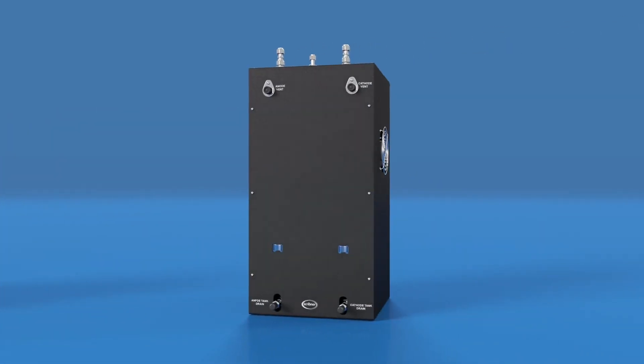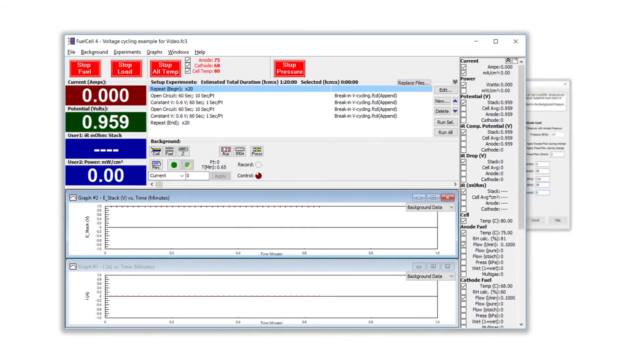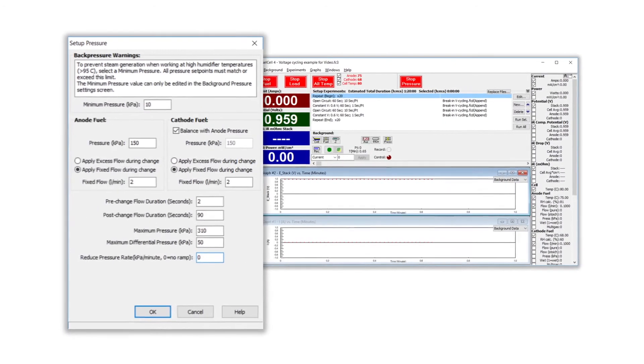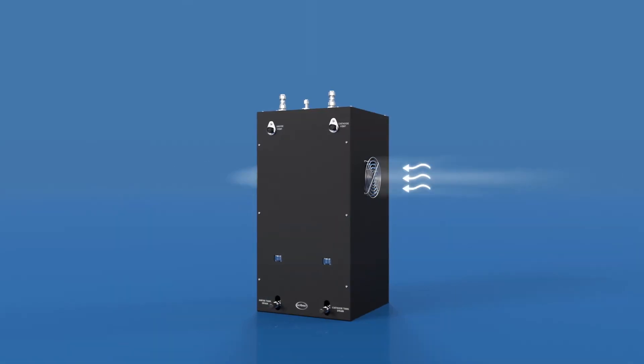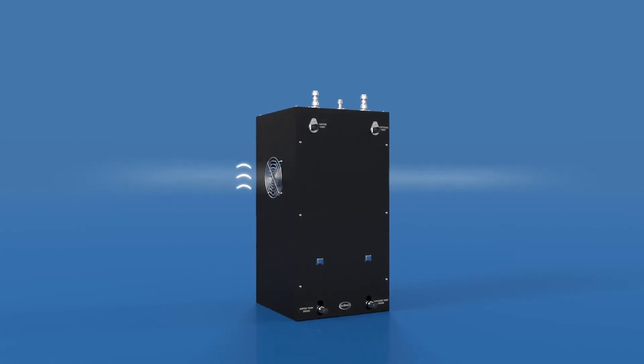The automated back pressure unit permits hands-free pressure control. The anode and cathode pressure are independently set and controlled through Scribner's fuel cell test system application software. The automated back pressure unit also has the advantage of the operating pressure being included in the data set. It is also designed for higher gas flow rate and high dew point testing.